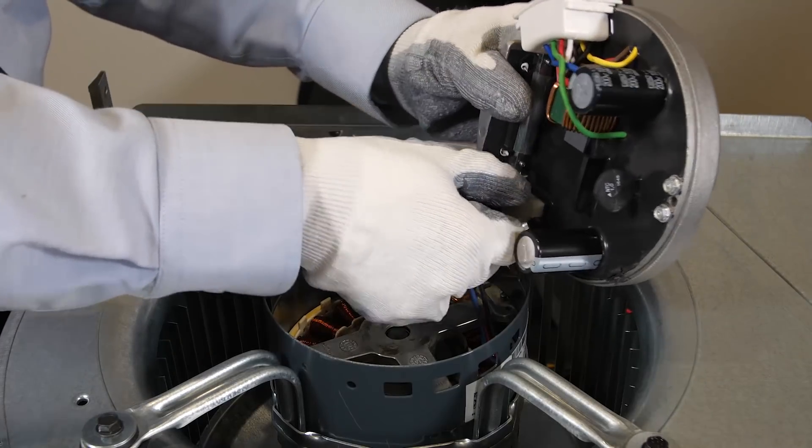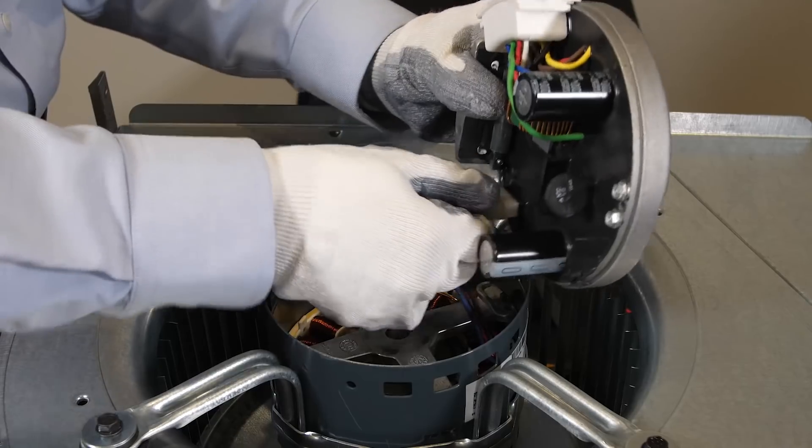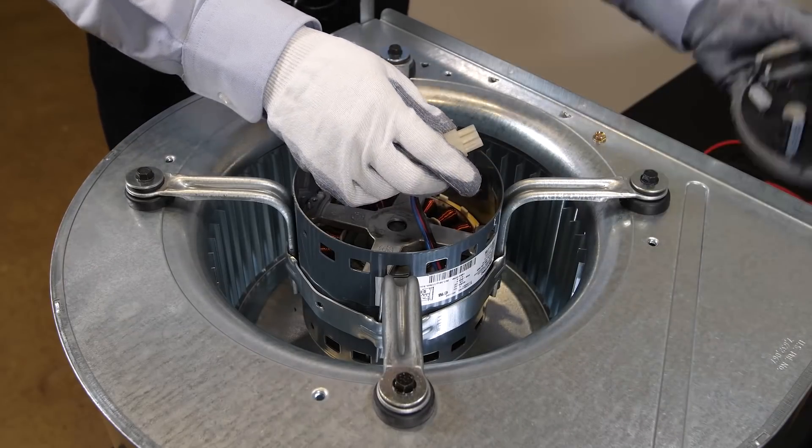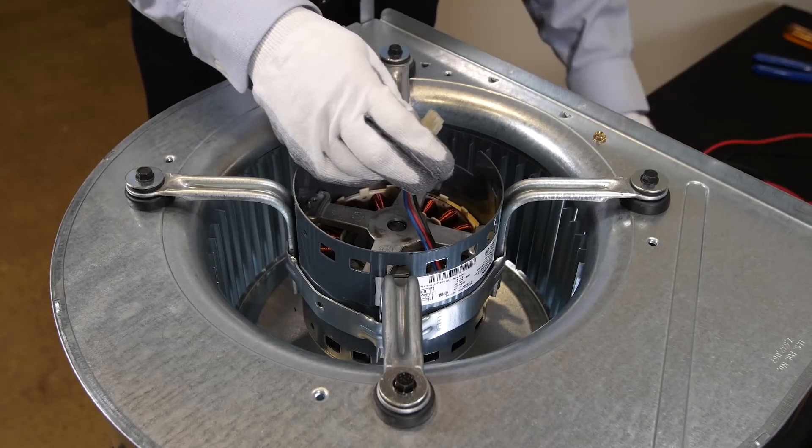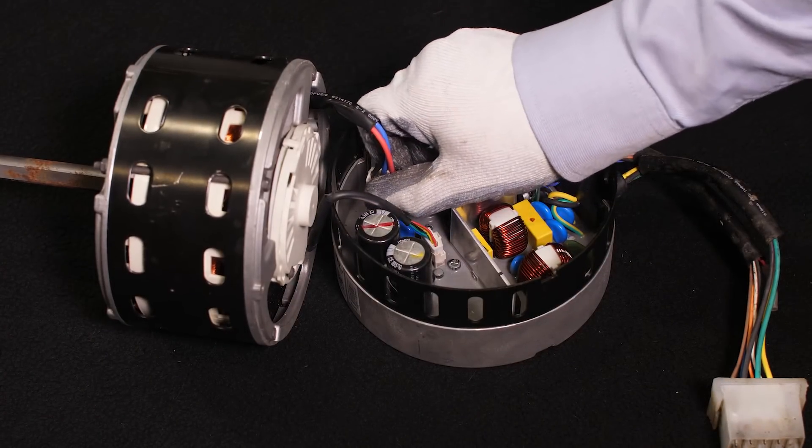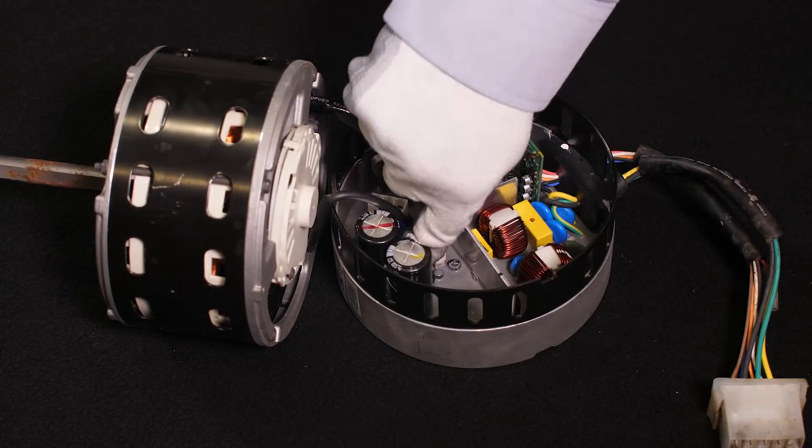Disconnect the three pin motor connector from the existing control and be careful to depress the latching mechanism before pulling the connector away from the control. Avoid pulling the wires. Depending on which type of tap select ECM motor you have, you may have an additional plug to remove.